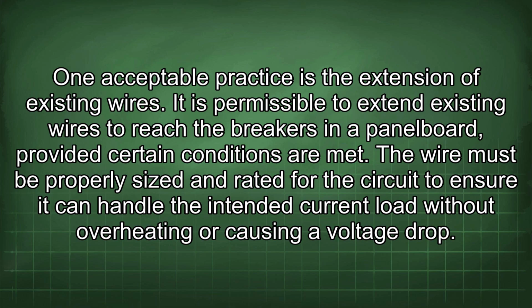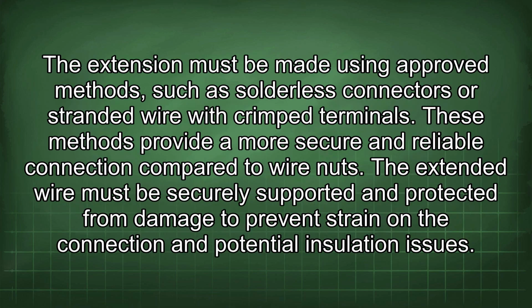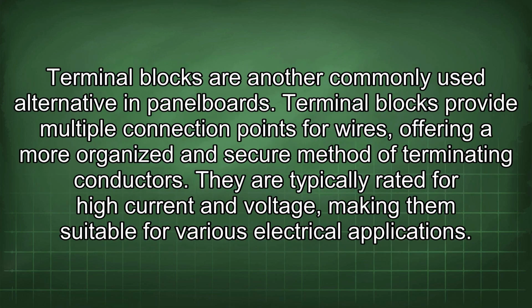The wire must be properly sized and rated for the circuit to ensure it can handle the intended current load without overheating or causing a voltage drop. The extension must be made using approved methods, such as solderless connectors or stranded wire with crimped terminals. These methods provide a more secure and reliable connection compared to wire nuts. The extended wire must be securely supported and protected from damage to prevent strain on the connection and potential insulation issues. Terminal blocks are another commonly used alternative in panel boards.